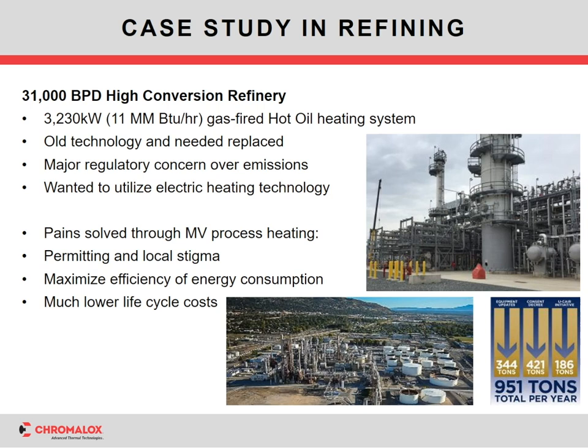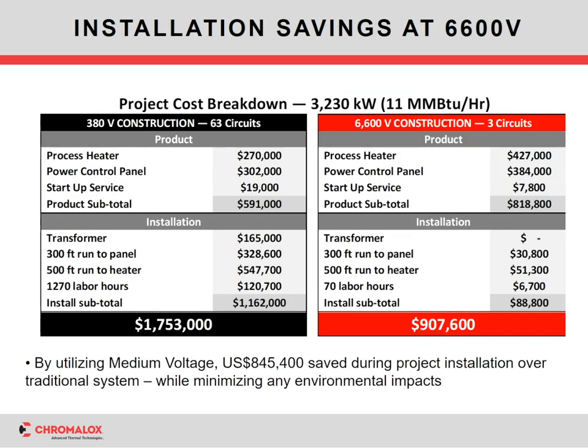So again, their choices would have been utilizing a low voltage system out there, which would have been fairly costly. What medium voltage was able to do was maximize the energy consumption, allow installation of medium voltage equipment at a low price point, and totally bypass the permitting process, as they didn't have to worry about putting in another stack or getting a waiver on their pollutions for the area. So we looked at a case study for them.